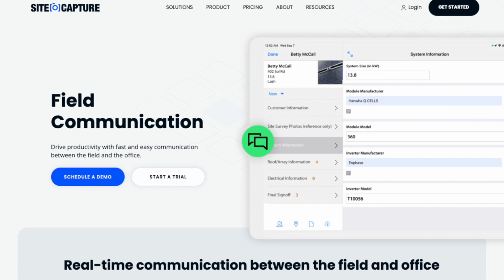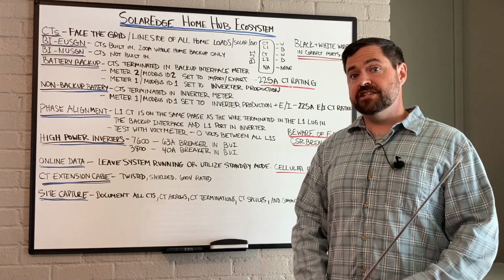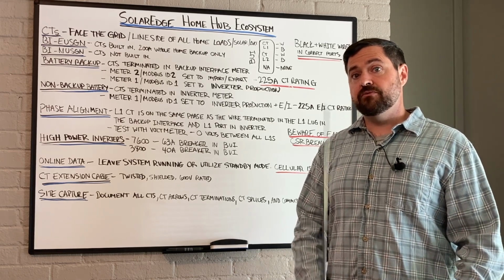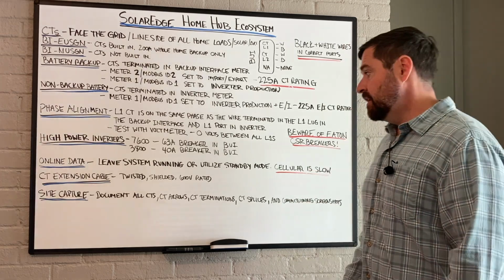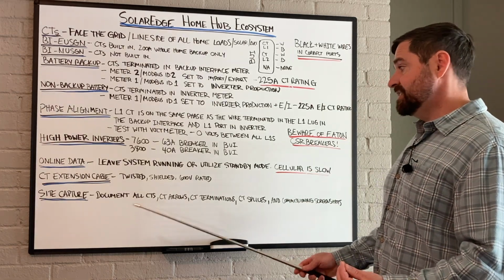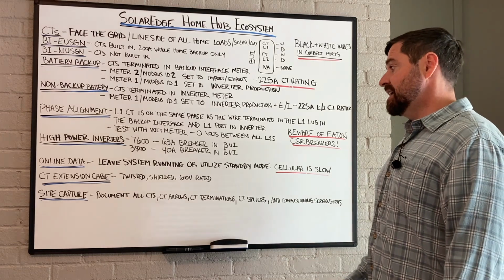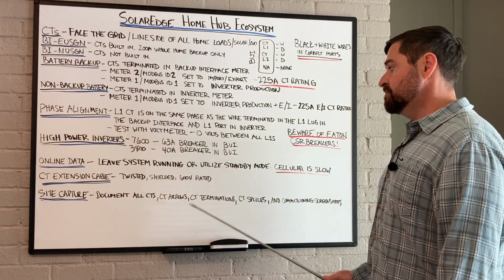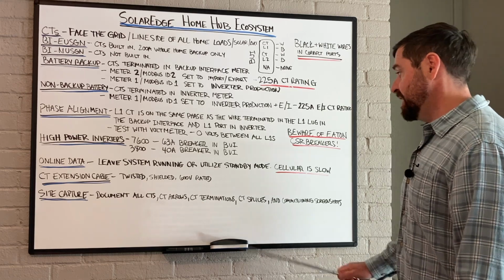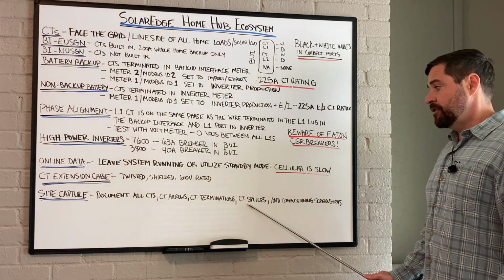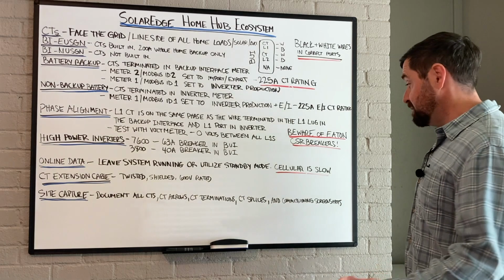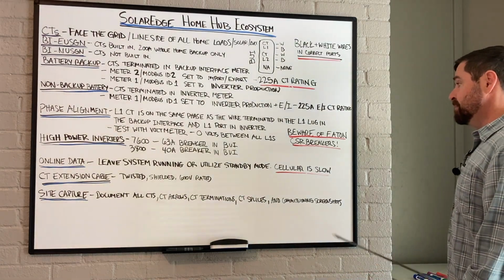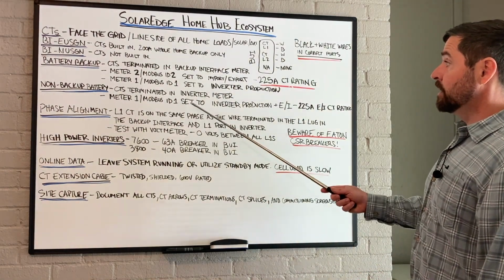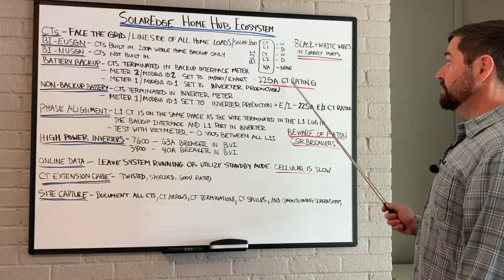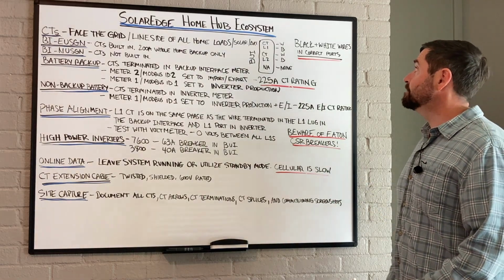Lastly, site capture. We need site capture filled out completely. Every single section. Please have your techs use it on site. Read through every single section carefully, especially in regards to CTs. We need all CTs documented. We need to see the CT arrows. We need to see the CT terminations. We need very close-up photos of the CT splices if you're splicing CTs, and we need those commissioning screenshots showing that the meters are set up correctly and the CT ratings are set up correctly.